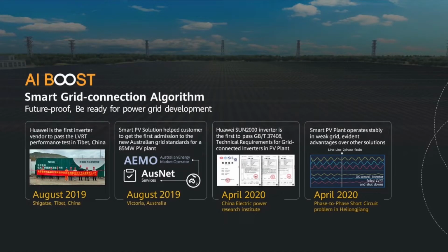Besides the testing results, we know that Australia's new standard in February 2019 is the world's most stringent power grid standard. Huawei helped our customers to get first admission to this new grid standard for a 85 MW PV plant in Victoria. The project time for this project is only half of other solutions. And in China, the Huawei SUN2000 inverter is the first to meet the new technical requirements for grid-connected inverters, which call for high requirements on high voltage ride-through, low voltage ride-through, and frequency adaptation.